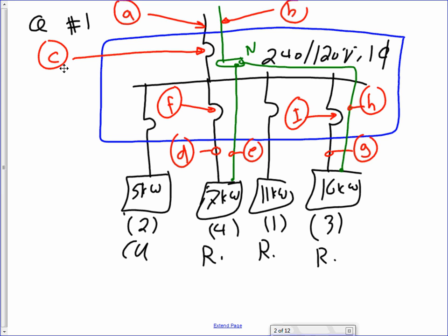The demand for these two under C. There are more, they're under C and they're different sizes. Do you guys remember what we do if they're under C, different sizes? We find their average and we increase the demand 5% if the average is more than 12, if you guys remember that. So here's what I'm going to do.